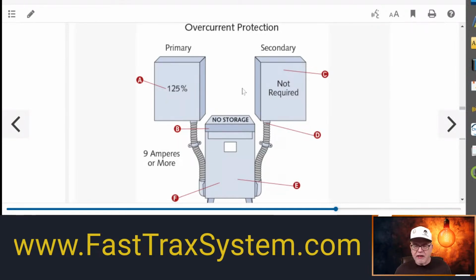Now, one of the questions I get from folks is, Paul, do I treat these conductors in all cases at 125%? Well, the good answer to that is, from an engineering design standpoint, the answer would be yes, I'm going to treat those at 125%. Even if you see later where I can go up to 250% on a primary. The thing is, this takes care of itself, so you don't have to overthink it, okay?